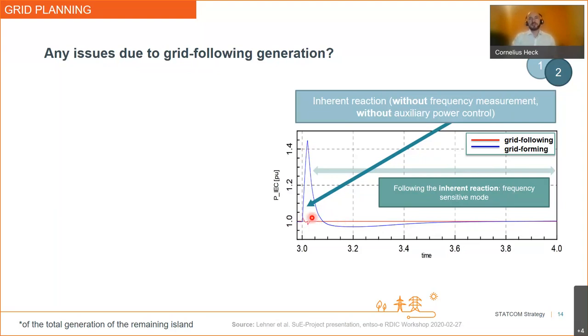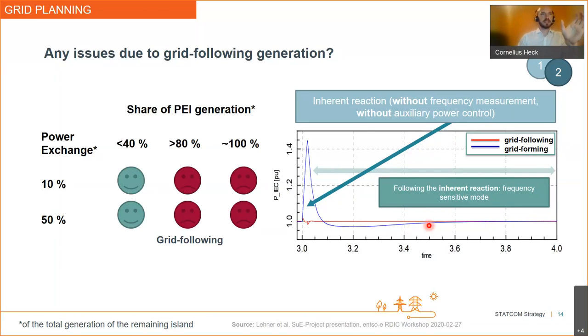Of course, after the first few hundred milliseconds, grid forming and grid following is hard to distinguish between. And this is because in this area, overlaying characteristics come into play. So here is the frequency sensitivity mode, or really fast frequency control, if you want to call it this way. So we had a project in Germany to determine what's a critical point of grid following generation in an otherwise synchronous generated dominated grid. And this is really, really easy to understand, I guess.